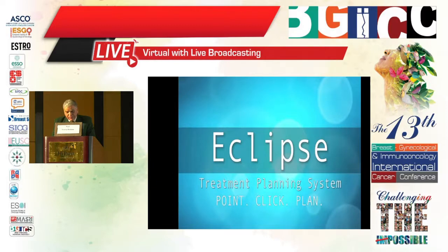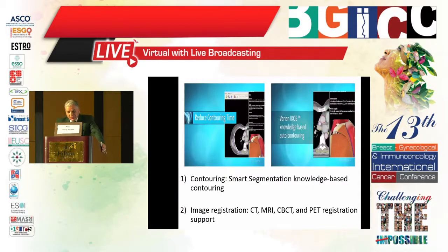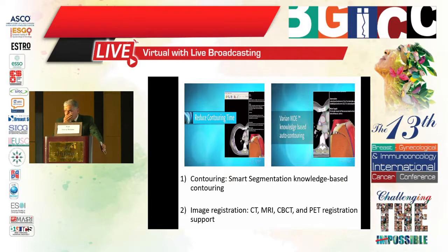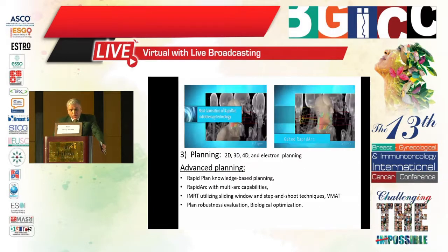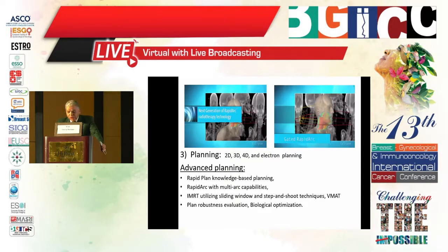Eclipse's slogan is 'point, click, plan.' It features smart segmentation and knowledge-based contouring, which reduces contouring time. Image registration from CT, MRI, CBCT, and PET is supported, enabling fusion of multiple radiology images for better tumor delineation. It can perform 2D, 3D, 4D, and electron planning, as well as advanced planning with RapidPlan, knowledge-based planning, RapidArc with multi-arc capabilities, IMRT using sliding windows and step-and-shoot techniques, VMAT, plan robustness evaluation, and biological optimization.